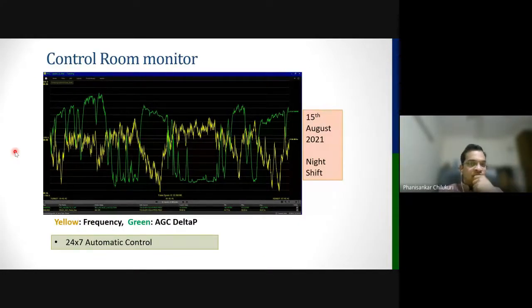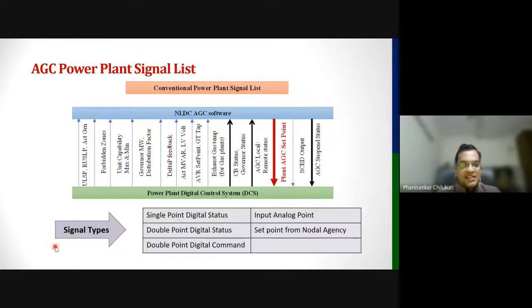This is our control room on 15th August 2021 night shift. There was little monitoring on this, but still AGC did up and down. The green is the AGC delta P, yellow is the frequency. Whenever the frequency is down, AGC increased generation. Whenever the frequency is high, AGC decreased generation. So it is a 24 by 7 automatic control. What AGC does is it changes the load set point of the generators. The RGMO, or the primary frequency response, gives inputs to the governor, but AGC changes the load set point of the generators.